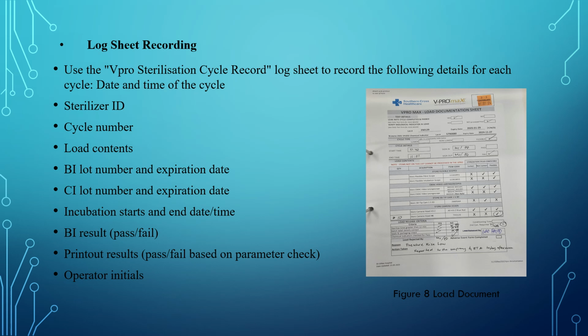Load BI content, BI lot number and expiration date are also written on the log sheets. Chemical indicators are also written on there, the chemical lot number of the chemical indicators and the expiry date, incubation start and end date on the sheets. BI result pass or fail, printout pass or fail, operator's initials. Every time the load comes out, each and every technician, we're going to sign the information and read the printout from the VPROs.